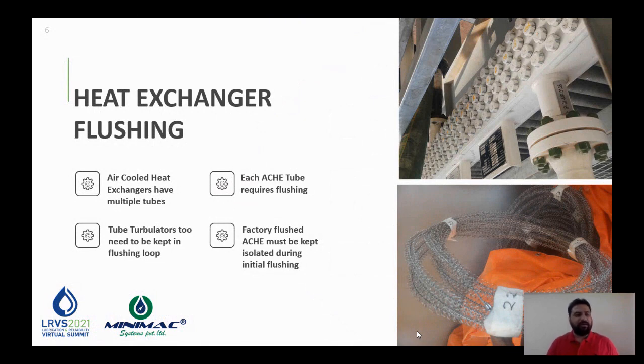While doing the flushing of heat exchangers, it's important to understand that these have multiple tubes, and if you do not calculate the correct flushing flow rate for these tubes, you might end up doing flushing at a much lesser flow rate than what is required.